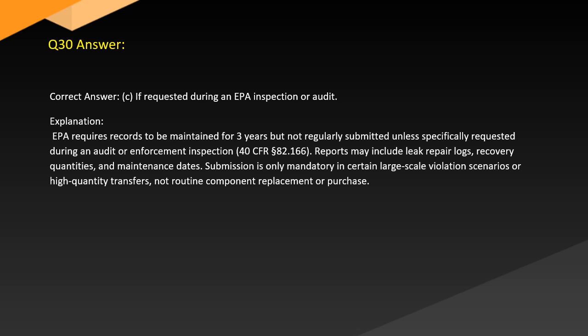Answer. Correct answer: C. If requested during an EPA inspection or audit. Explanation. EPA requires records to be maintained for 3 years but not regularly submitted unless specifically requested during an audit or enforcement inspection, 40 CFR 82.166. Reports may include leak repair logs, recovery quantities, and maintenance dates. Submission is only mandatory in certain large-scale violation scenarios, or high-quantity transfers, not routine component replacement or purchase.